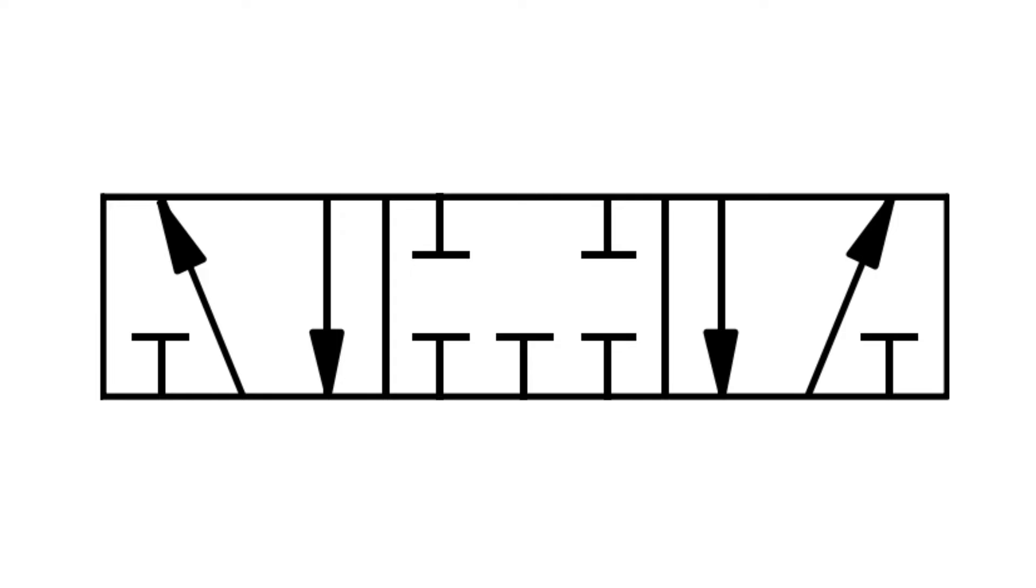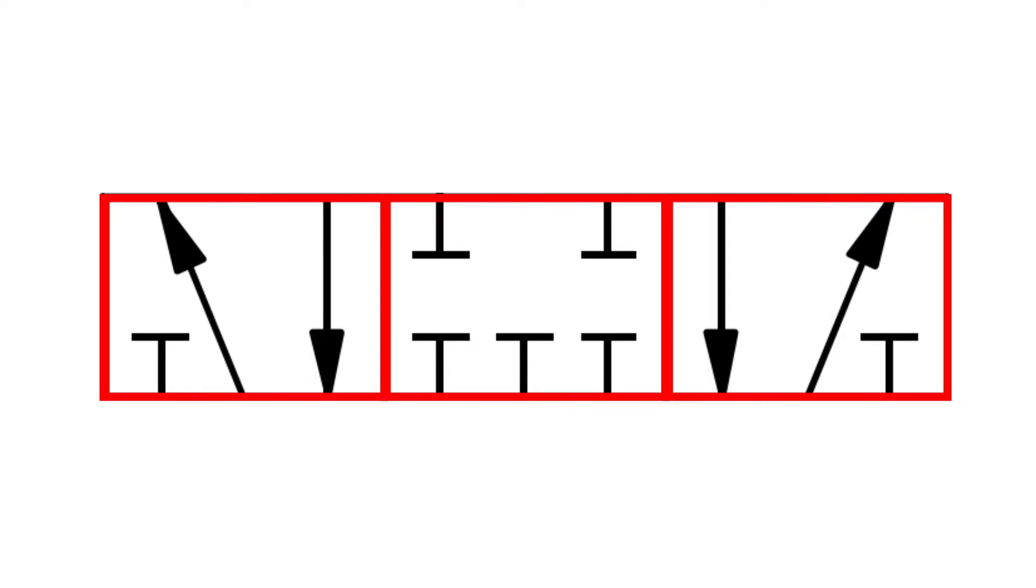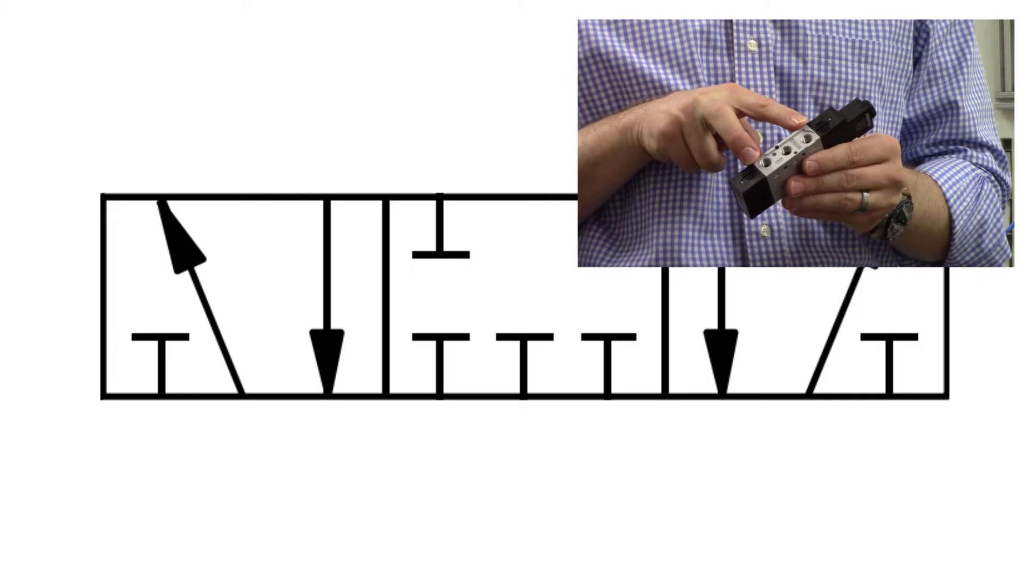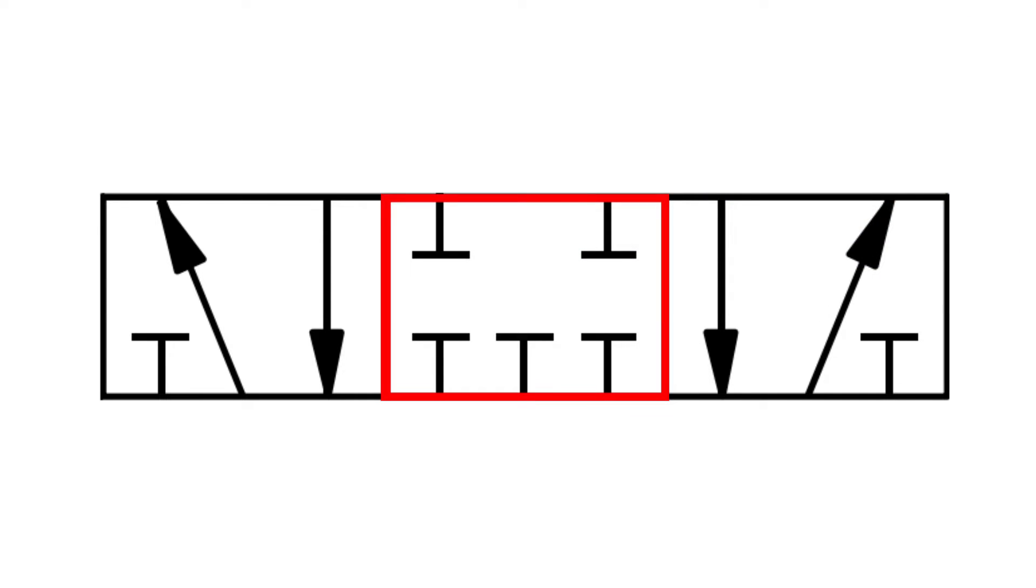A 5-3 valve is called a 5-3 because it has five ports and three possible positions. The two outer positions function the same way as a 5-2 valve, which we covered in this video. However, 5-3 valves also have a third position in the center, which can serve one of many unique functions.